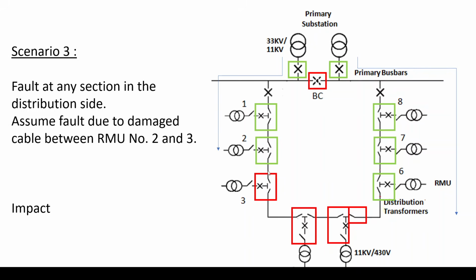Something happens here, whatever the reason, and the cable is faulty and does not deliver power to the remaining part of the ring. So as we said, in a normal operating scenario, this one's fed from here, this one is fed from here. So this section is up and running. It's not affected by this. Now I had a problem in this section on the distribution side this time. So this one, since it's now faulty, the power will not continue to reach here. These ones are red in color and they are disconnected. Let's see again how the RMU would help us to overcome this and enable us to repair that fault without affecting the power distribution in the network.